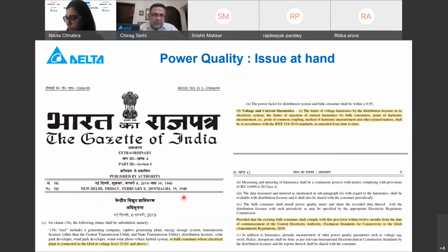In February 2019, this topic was given more emphasis when the Central Electricity Authority came out with a gazette notification saying that all bulk consumers who are tapping power at 33 kV and above need to comply with voltage and current harmonics as specified by IEEE 519, the latest 2014 standard. So this automatically mandates that all such bulk consumers, and of course railways is also one of them, need to abide by these stipulations as per the Central Electricity Authority.